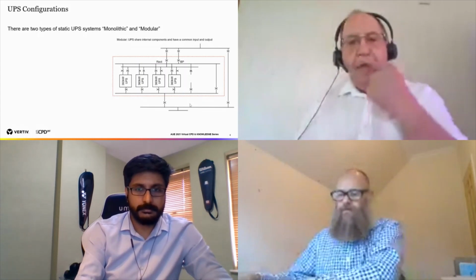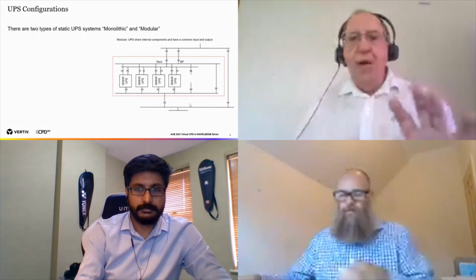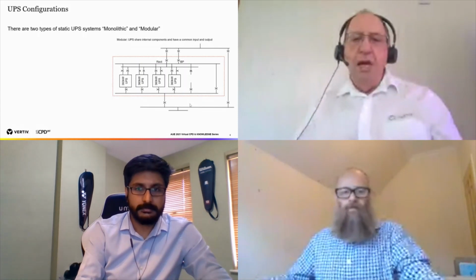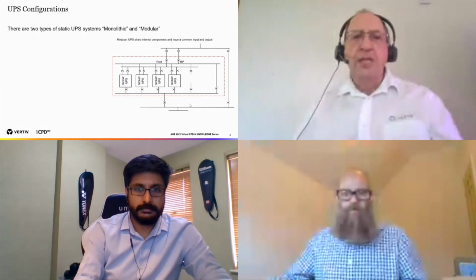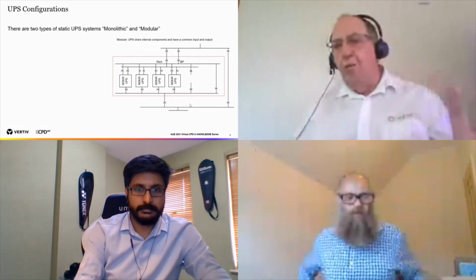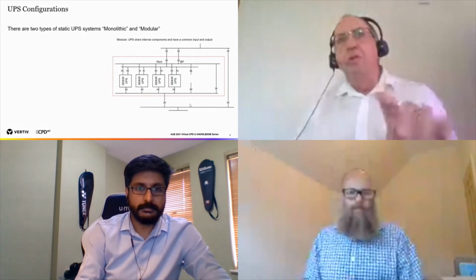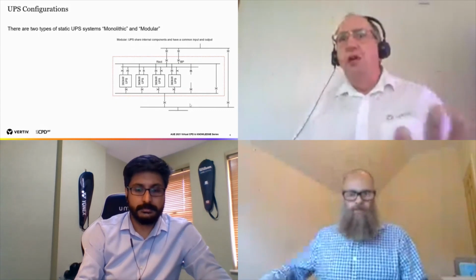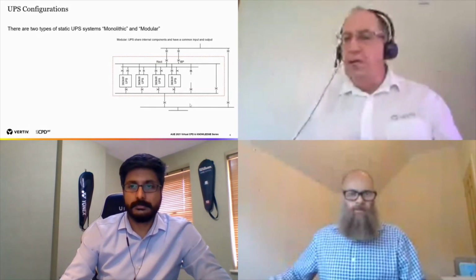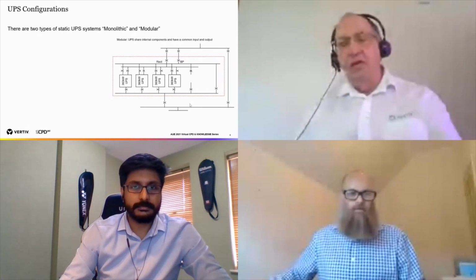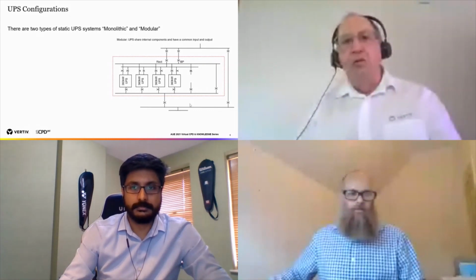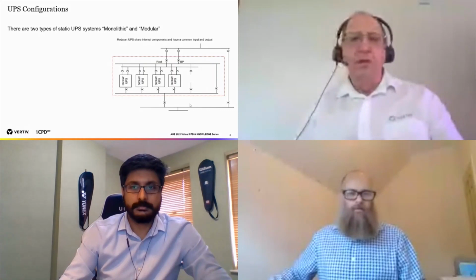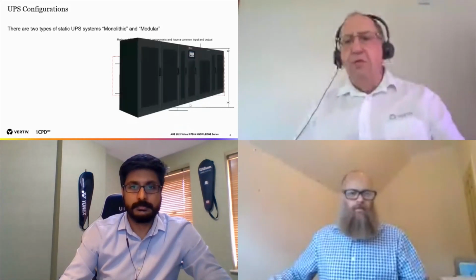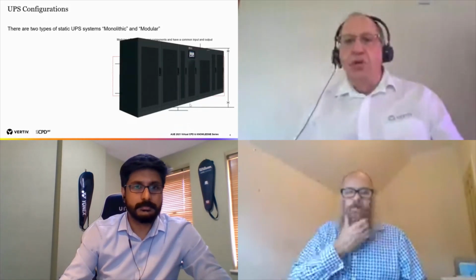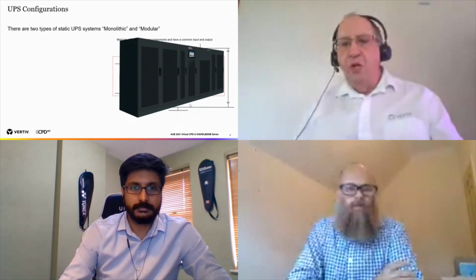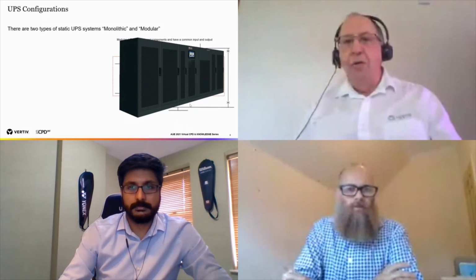So these systems tend to be where the industry is at the moment, and the modular UPS, if you pay a little bit more money, those modules can be removed and inserted hot. So you don't need to turn off the UPS to do servicing. You don't need to turn the UPS off to change a module, provided you follow the right instructions, etc. So that's a picture of what a modular system would look like. Each one of those black boxes is part of the module.